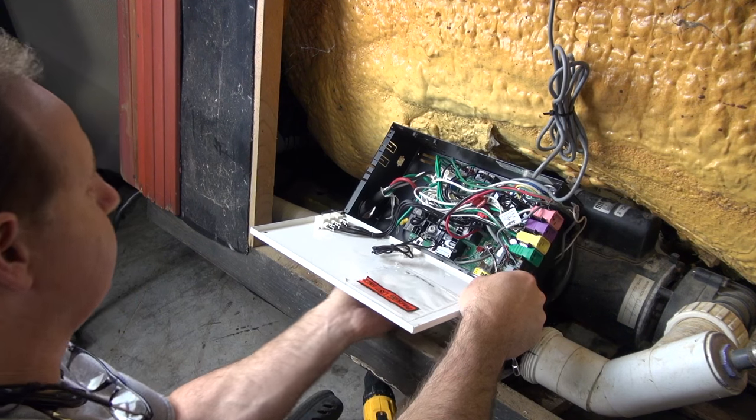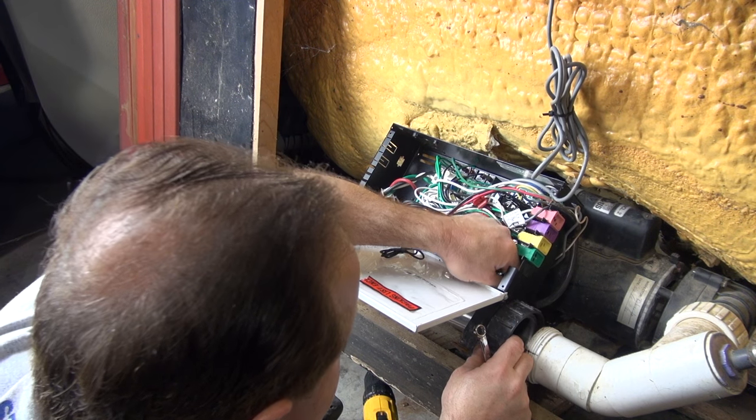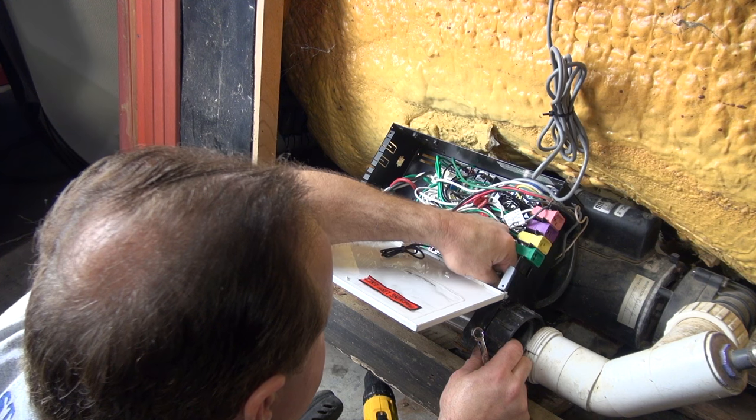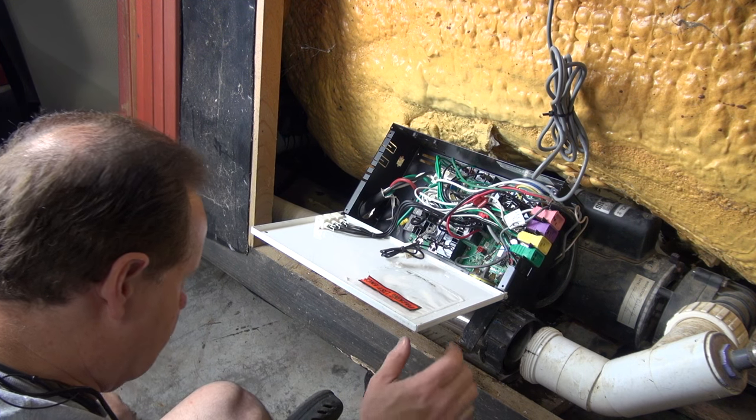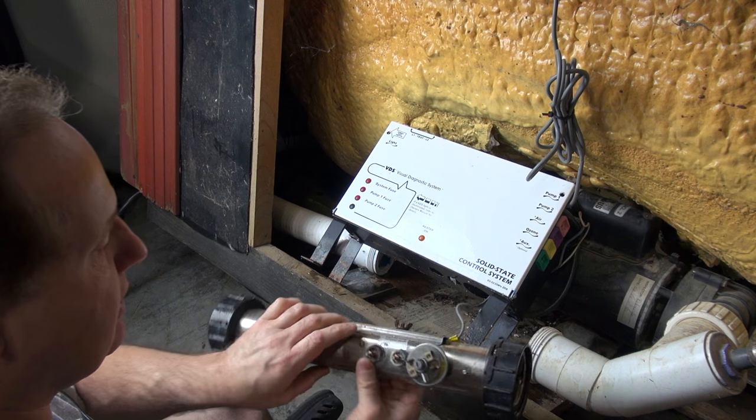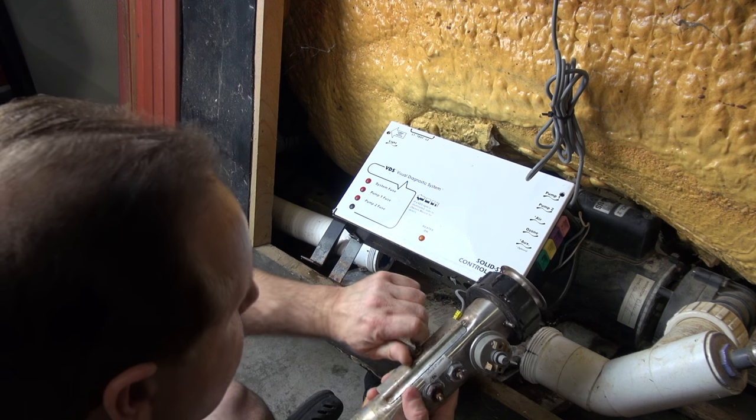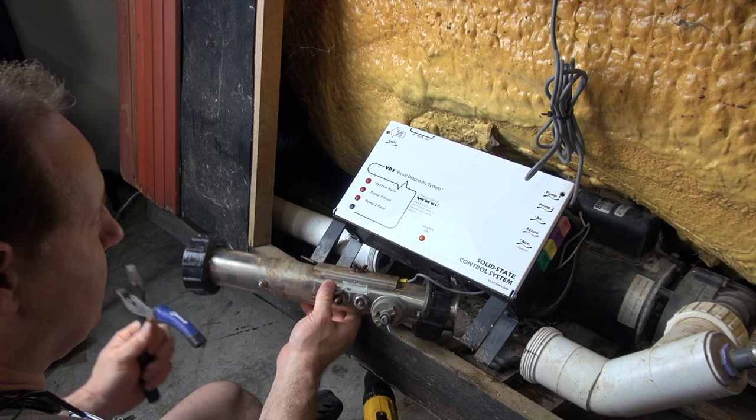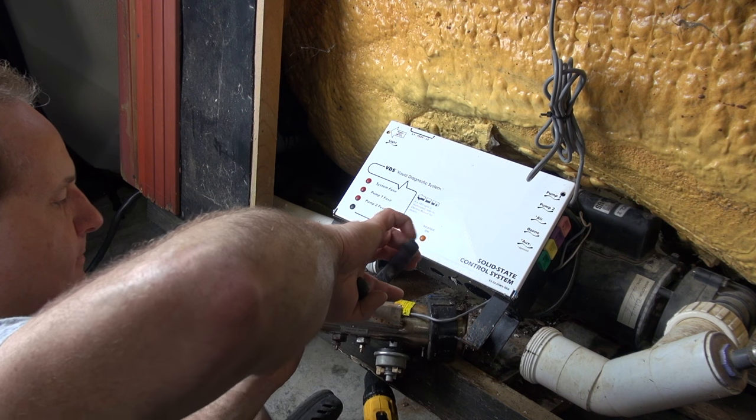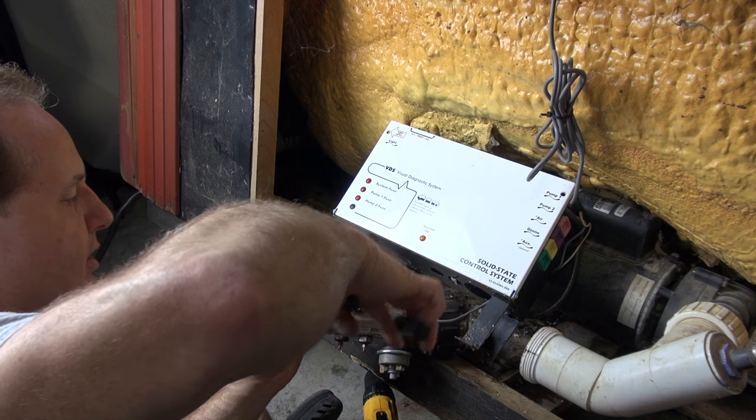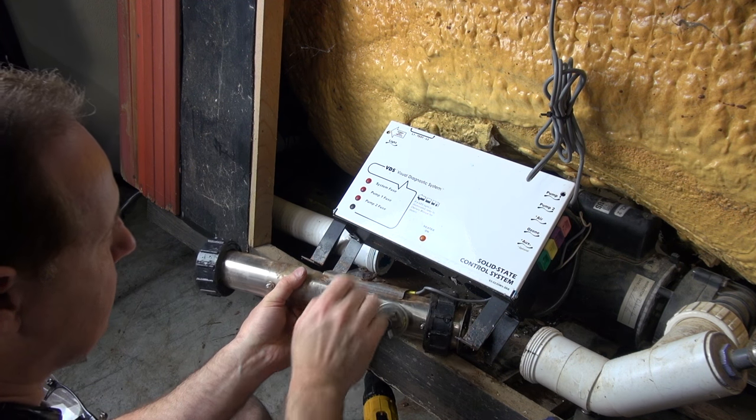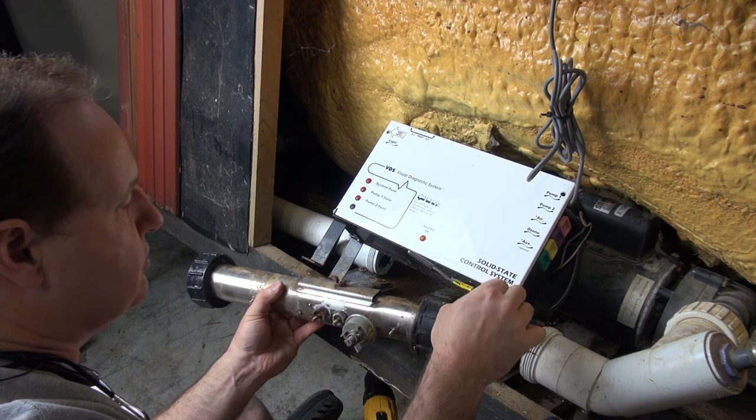So, there's always going to be one problem somewhere, there it is. And usually there'll be a high limit on the heater somewhere, pinched on, and this particular one I'll show you, the high limit is right here, pinched inside this. And you see this thing is pretty rusty, this heater is, so we're going to clean it up nice, change the heater element. And a telltale sign that the heater element itself is bad is that right there, you see that rust and that discoloration, that is a sign. So there's your high limit.